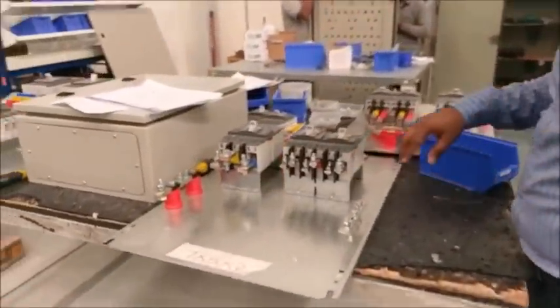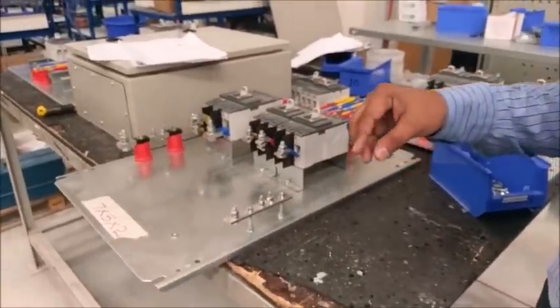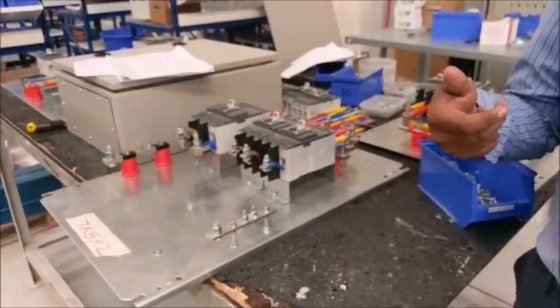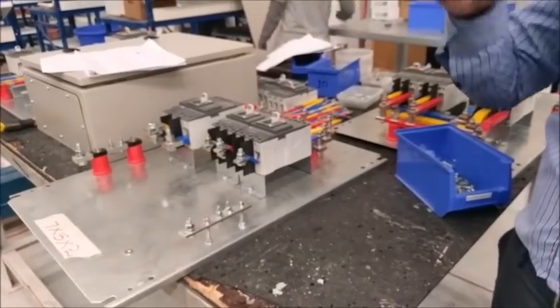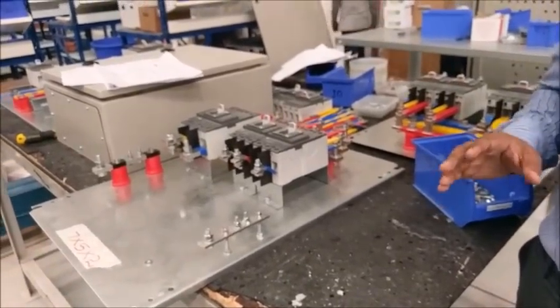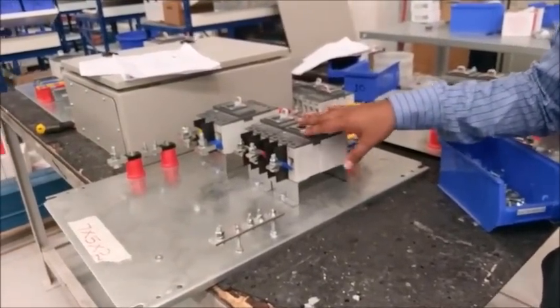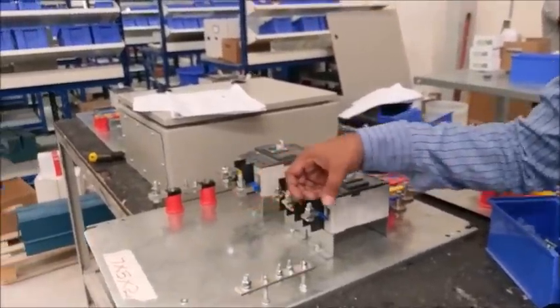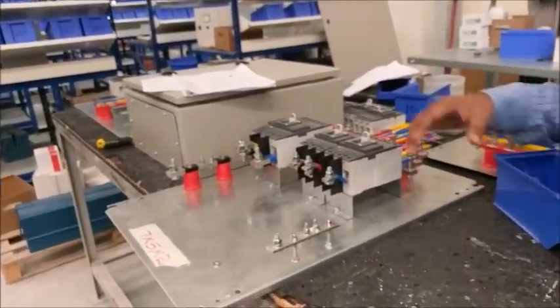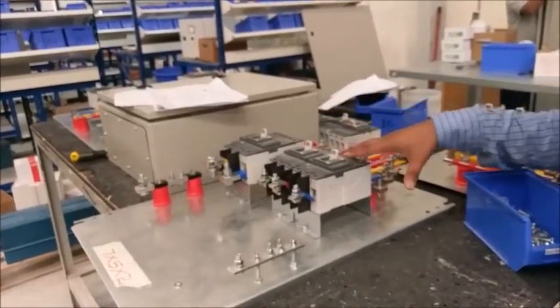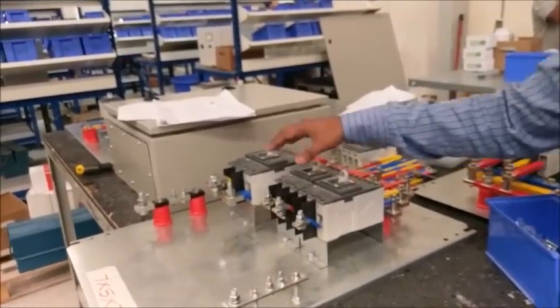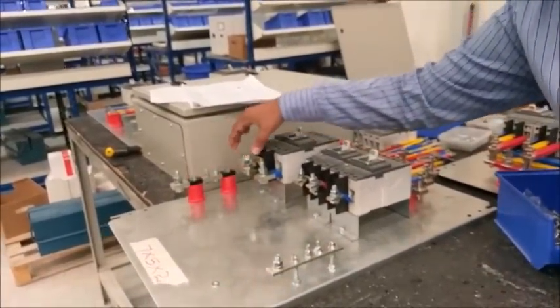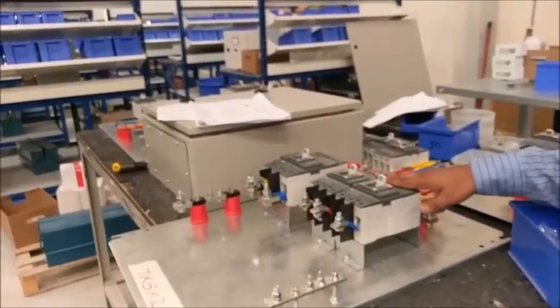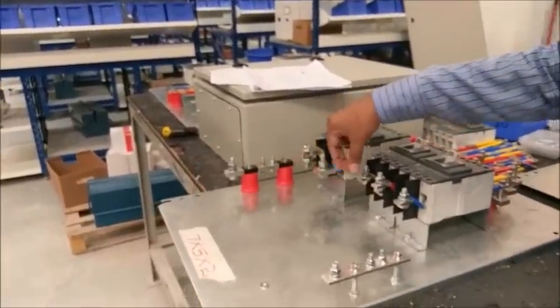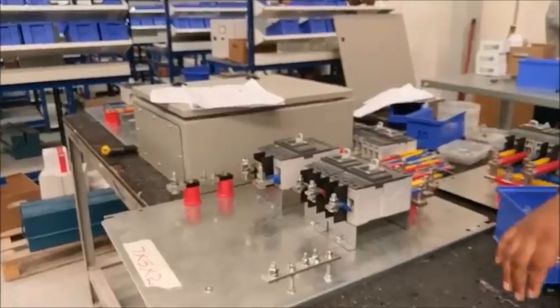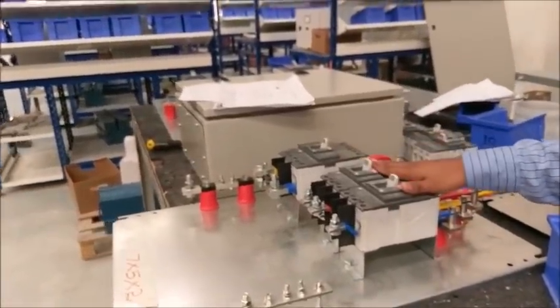Here we can see this is actually customized, where the client has a bigger cable size and there is some restriction in the standard SMDBs. So we cannot manufacture in a standard SMDB if the cable sizes are too much more. For that we make some customization like this. This is the incoming cable and these are two outgoing. So the cable will come directly and plug here. This is a molded case circuit breaker, MCCB.